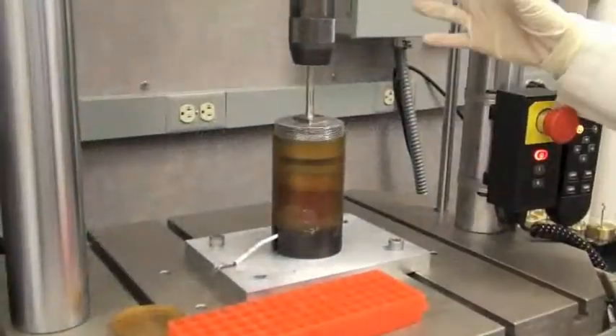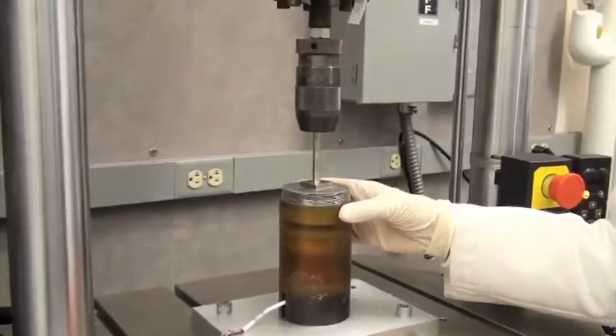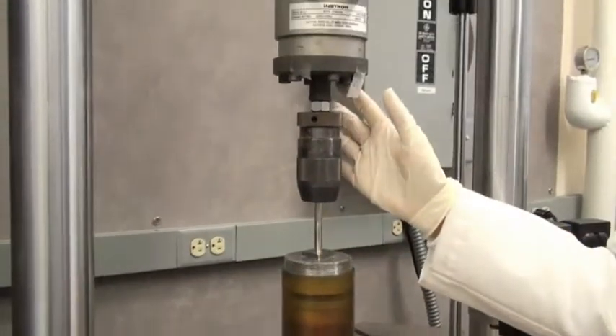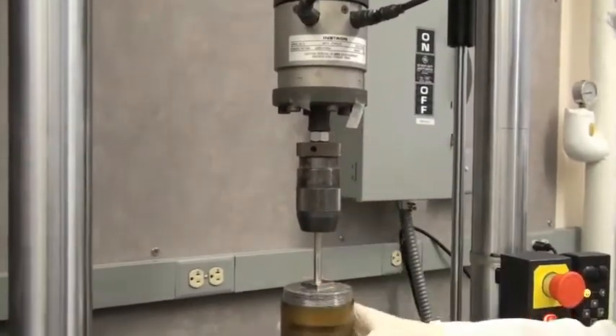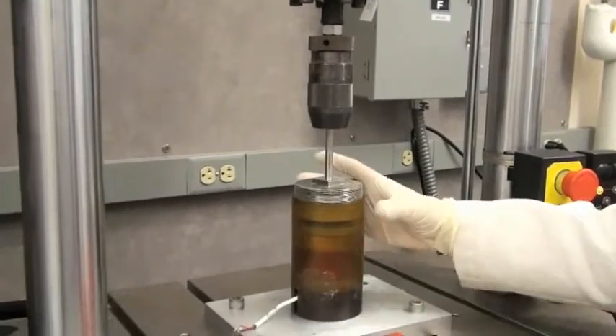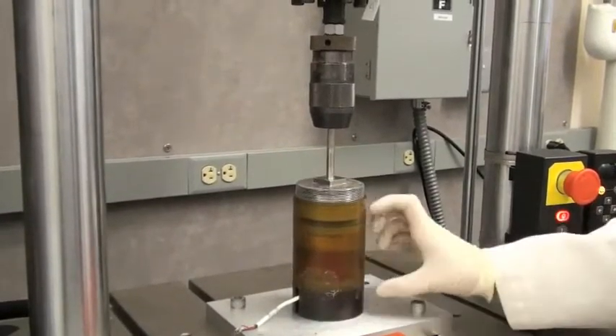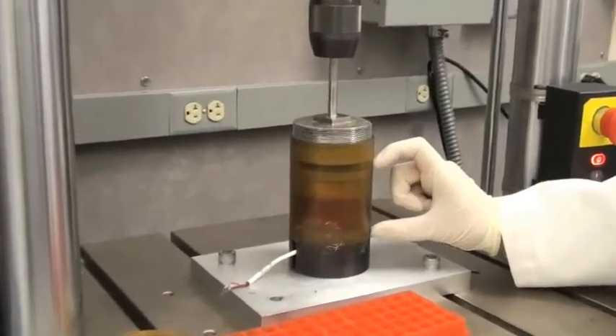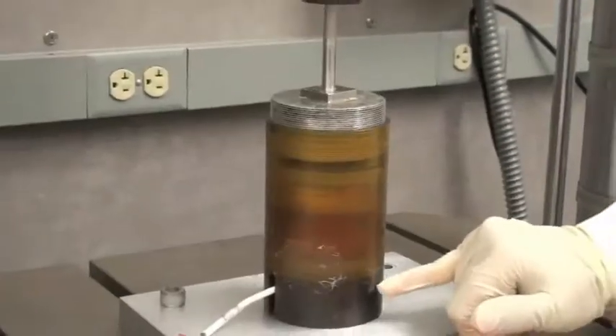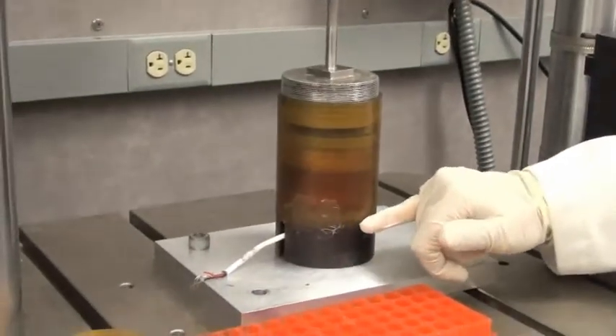When we come back from the medical campus, we start our mechanical testing. We use the Instron machine to apply a compressive load. Right now I have the sample holder, with my vertebral segment inside it, and there is a load cell placed underneath to record the loading.